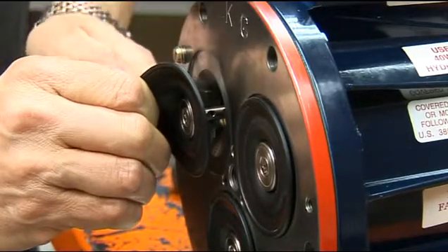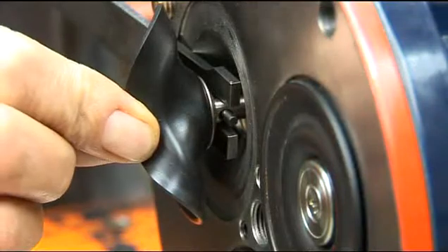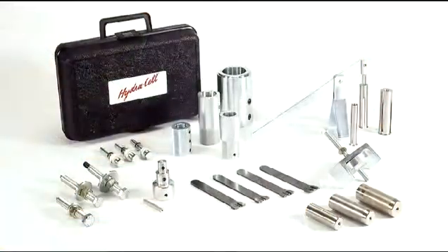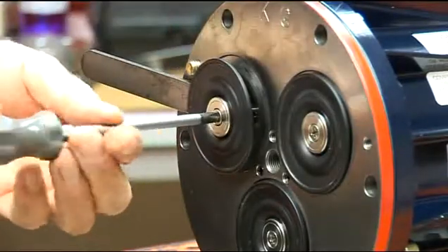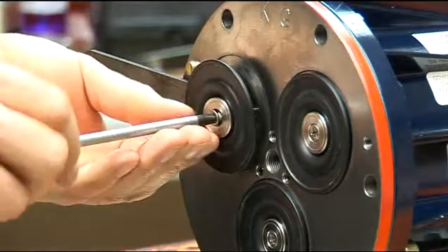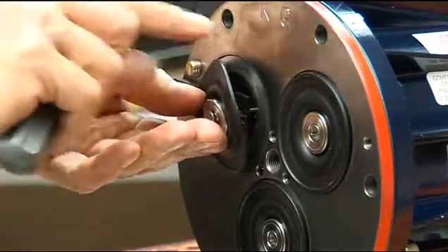Insert a plunger holder through one of the holes to hold the diaphragm up. The proper size plunger holder is included in the Hydra-Cell toolkit. Remove the screw, o-ring, and follower in the centre of the diaphragm, and this will allow the diaphragm to be removed for inspection.